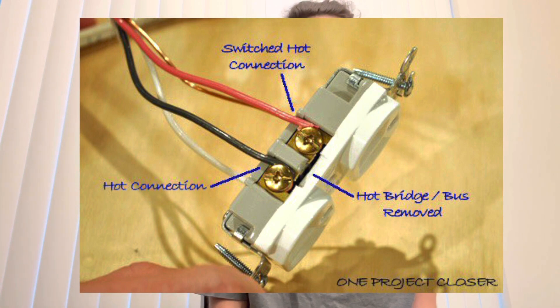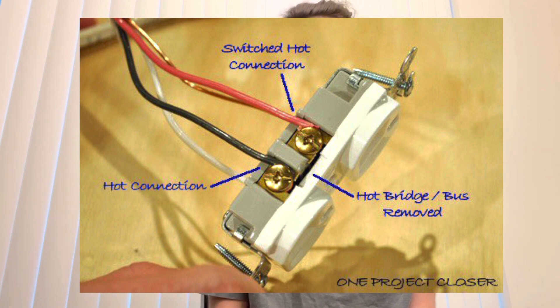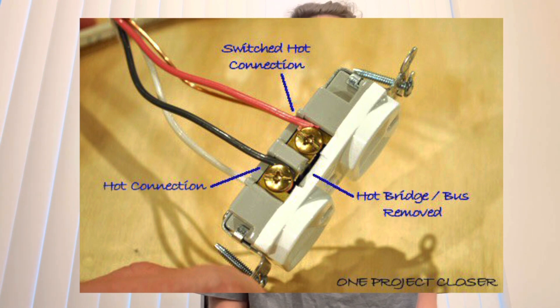Going through the video I did miss a few things. One of those was the half hot, which is the receptacle that has half of the plug controlled by a switch — we've gone over this in the garage several times. Basically it's just a regular receptacle with the hot tab broken, then a constant hot on the bottom and a switch wire on the top for the switch application.